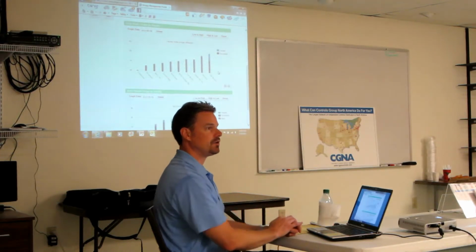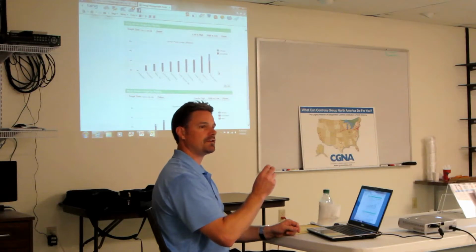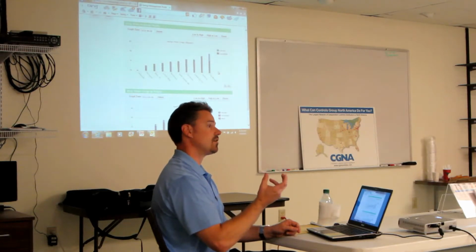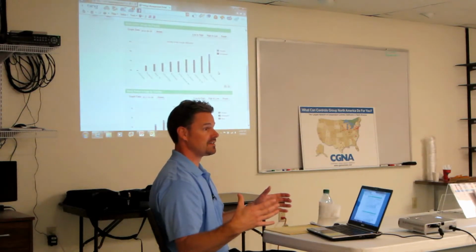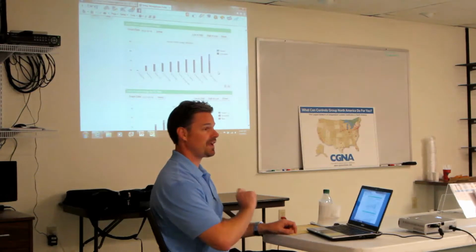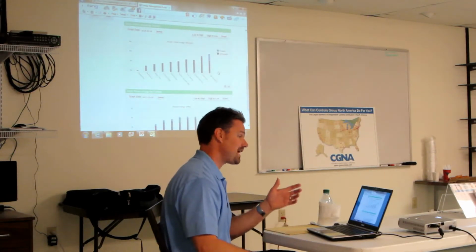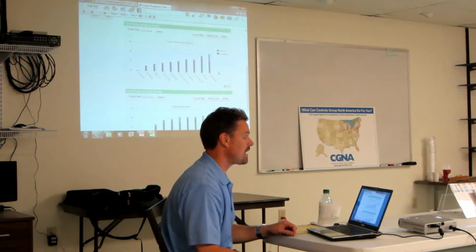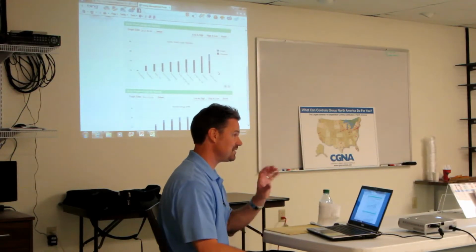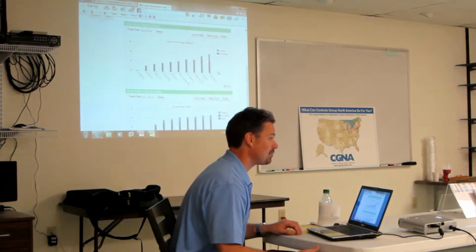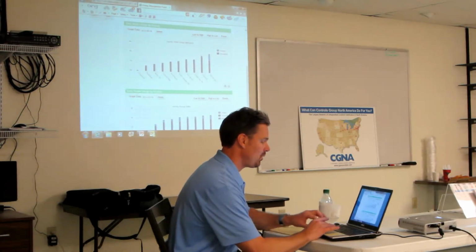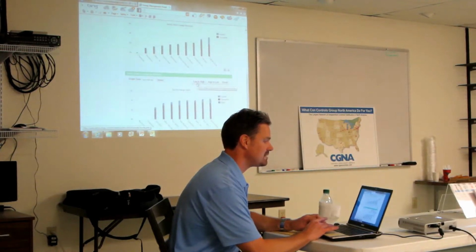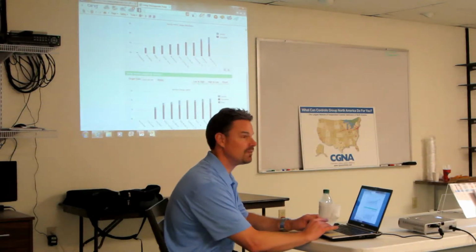Well, I drilled into it earlier and took a look at it. Instead of having their HVAC fans set to auto, they've got them at on. So even though they've got great setbacks at night, so the compressor's never turning on, the fan never shuts off. So that's something that their facilities manager, who I'm surprised hasn't caught this yet, looks at this every day, would see that and go, okay, either they're doing that on purpose, there's a reason maybe, or he hadn't caught it yet. My point is that this lets you know there's issues, and then you can drill into them and find them.